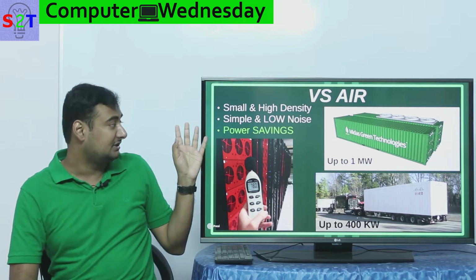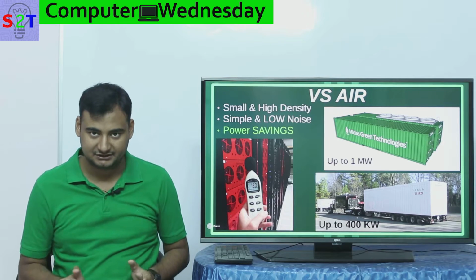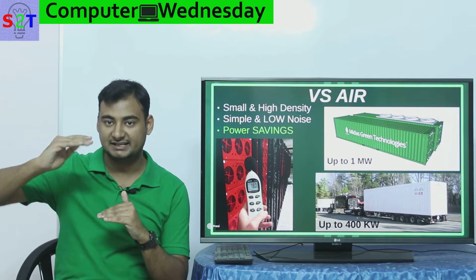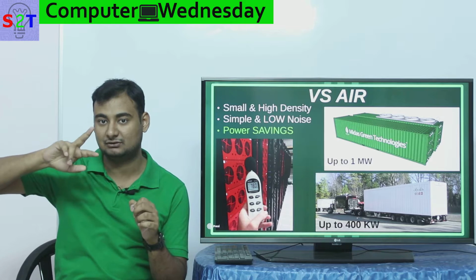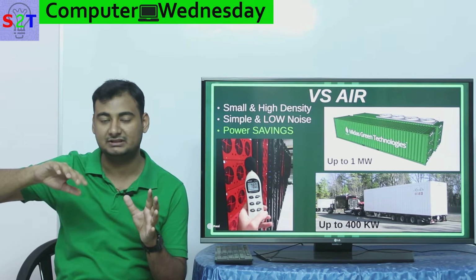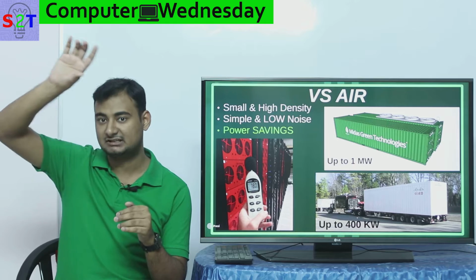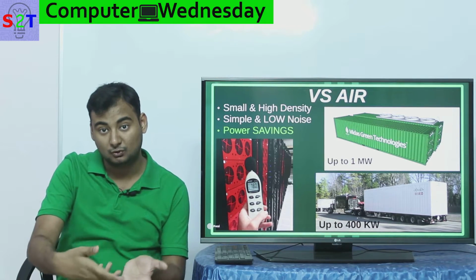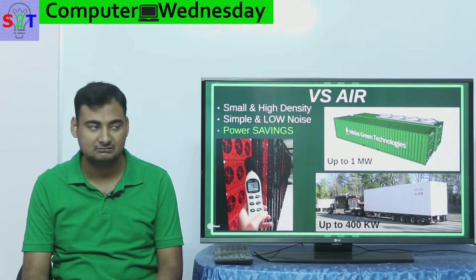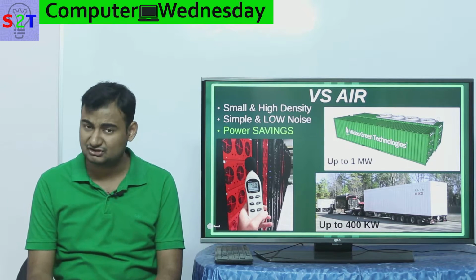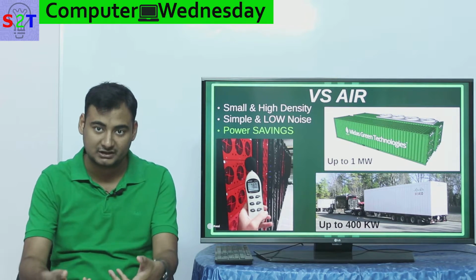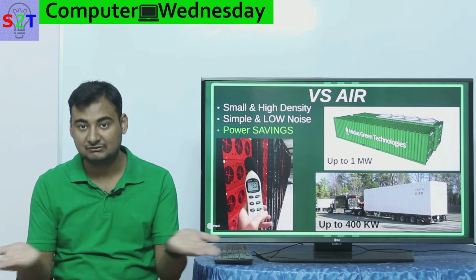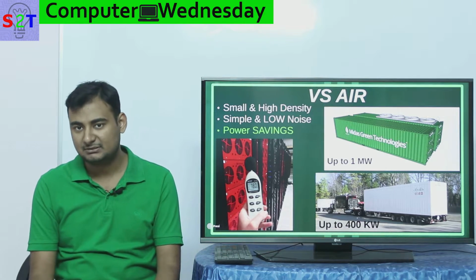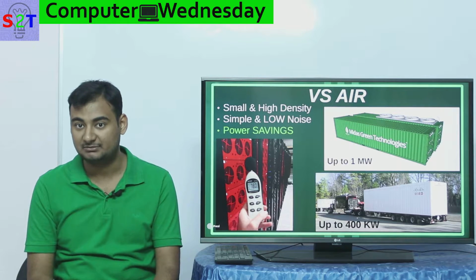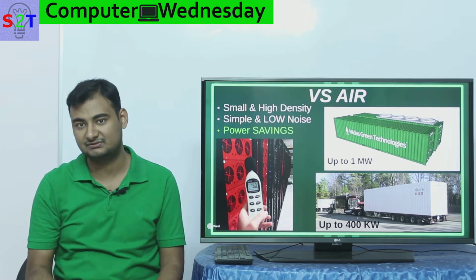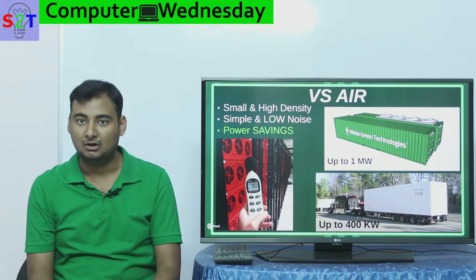Second, it's very simple for architecture. As many of you know, because hot air rises, all air conditioning units have what's called a two-path cooling solution. Basically, they collect the hot air from the top and distribute the cold air from the bottom. This was not done in old data centers, but nowadays it's almost compulsory, because the cold air is released from below, meaning your floor is elevated. It does have some extra advantage: it allows you to route cables under the floor, which is much easier to access compared to on top of the floor.